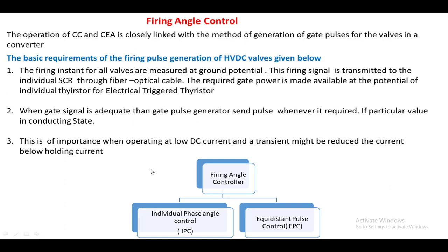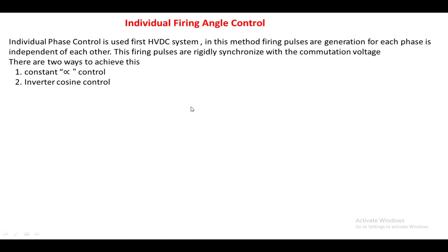The firing angle control is broadly divided into two types: individual phase angle control and equidistance pulse control. In individual phase angle control, the firing pulse generated for each phase is independent — that is why it is called individual phase angle control. The firing pulses are rigidly synchronized with the commutation voltage. There are two types under individual firing angle control: constant alpha control and inverter cosine control.